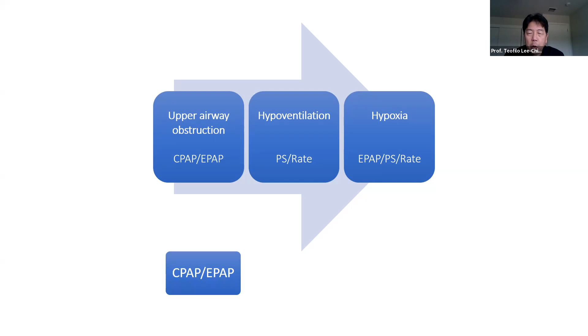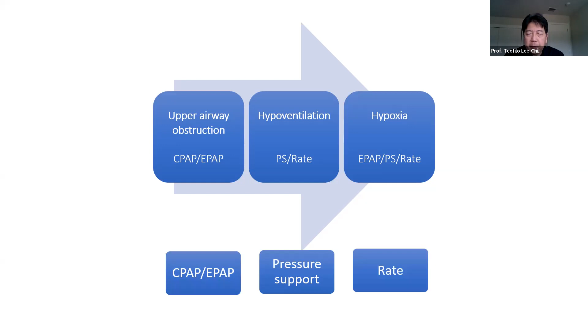So what we can do today with our devices is simply we can change the EPAP, CPAP. We could alter the pressure support. And of course, we can always add a rate. And with the three in mind, we have the first generation bi-level devices, the second generation volume assured pressure support, and the third generation volume assured pressure support with automatic EPAP. And what we have done is change from a BiPAP where you have to manually enter your EPAP, CPAP, pressure support, and rate to a second device where we have automated the pressure support. And finally, to the third generation, we have automated all three. Allow me to explain.